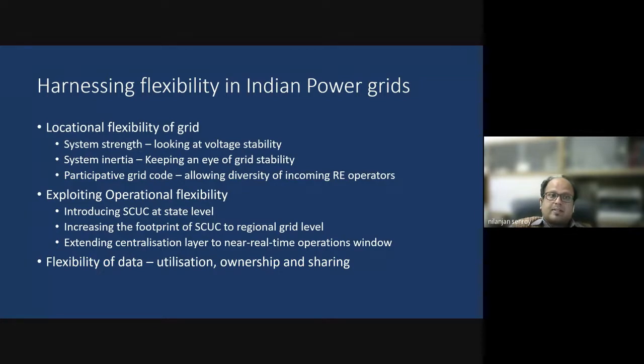So two different aspects of flexibility must be assessed. The first is the system strength, which is looking at the voltage stability, and the second is the system inertia, which is looking at the grid stability. So when we talk about the system strength, I hope you know that the system strength basically refers to the reluctance of the grid voltage to change in response to small perturbations such as switching on of a load or an equipment. So it is also directly related to the available three-phase fault MVA level, so short circuit strength.